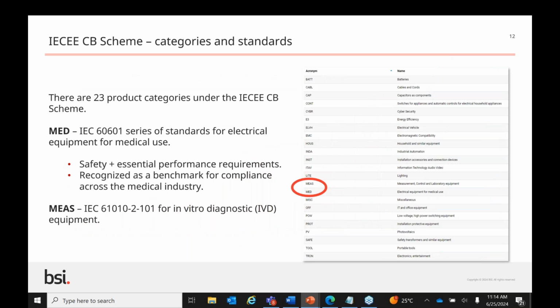So overall, there are 23 product categories in the IEC CB scheme, but medical products largely fall under two of those categories. The first is the med category, or medical. This is the series of standards that comprises over 70 individual 60601 standards or 80601 standards, and they set the safety and essential performance requirements. And the other category is MEAS, or measuring lab equipment. Unlike the 60601 series, which has lots of different standards, there is only one, which is 61010-2-101. This is just a single standard that covers in vitro diagnostics, or IVD, products. Next slide, please.